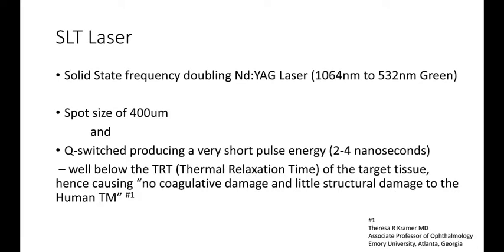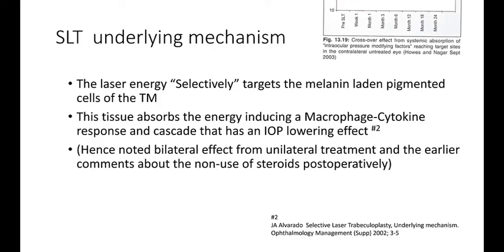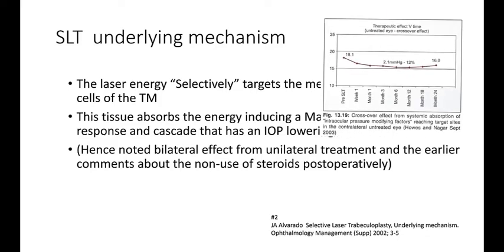Here is an example of an electron micrograph showing the minimal damage after the application of SLT. This is a solid-state, frequency-doubling neodymium laser with a spot size of 400 microns, Q-switched, producing a very short pulse energy, causing no coagulative damage and little structural damage to the human trabecular meshwork. The laser energy selectively targets the melanin-laden pigment cells of the TM. This tissue absorbs the energy, inducing a macrophage cytokine response and cascade that has an IOP-lowering effect — hence the noted bilateral effect from our studies some years ago.